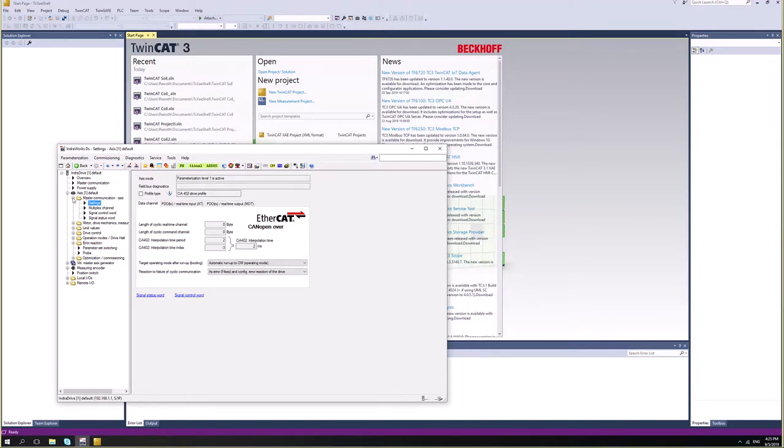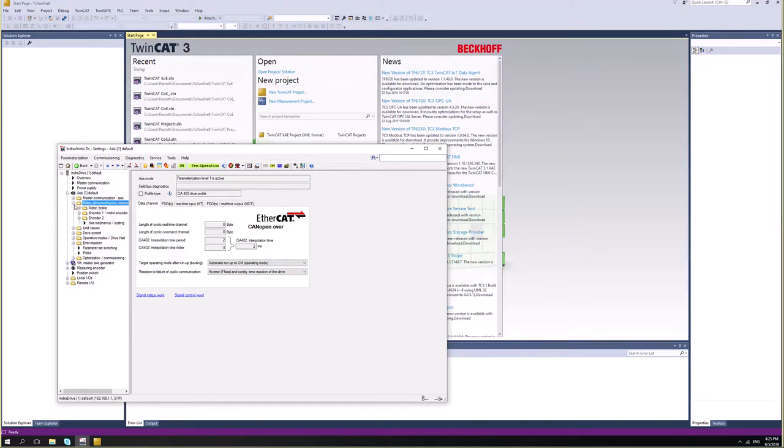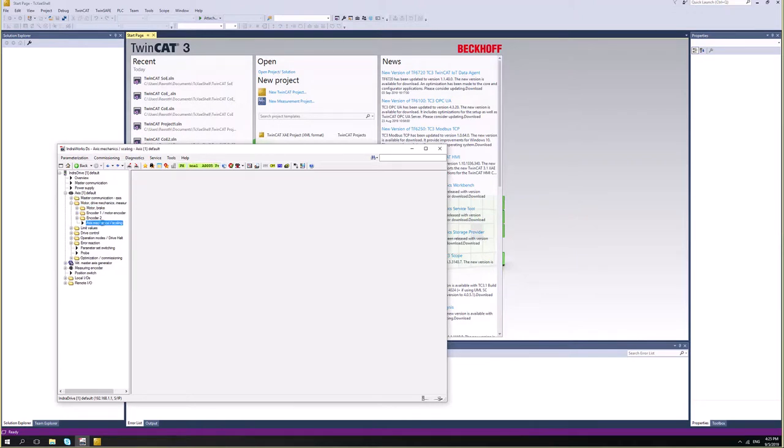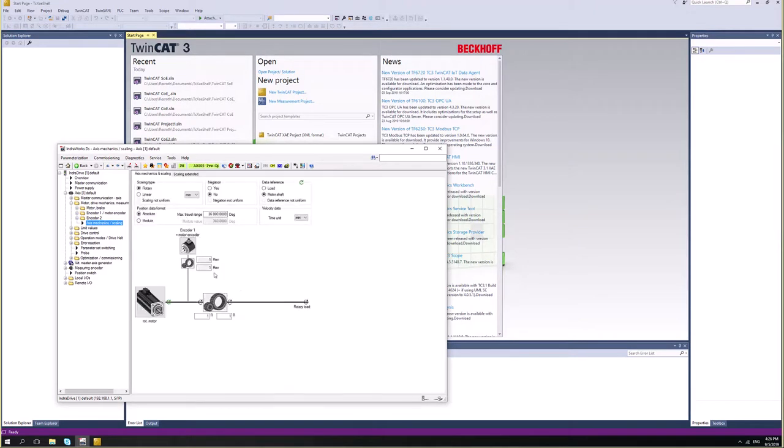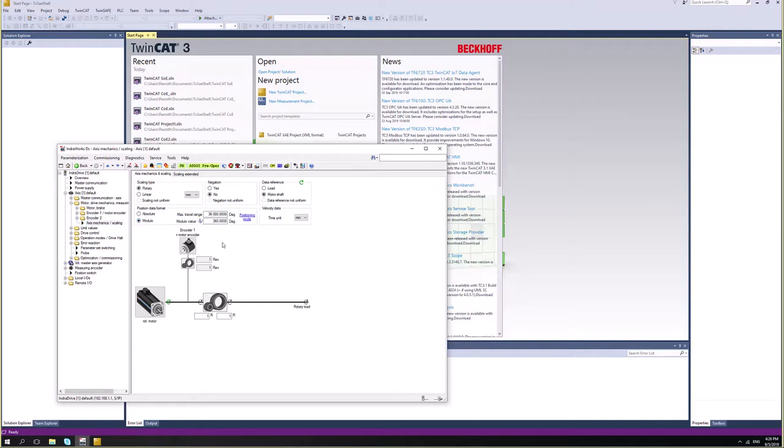Another thing that might be important for us is to check if our scaling, the mechanical, is properly configured according to our machine configuration. In my case it is configured as rotary and absolute. Let's say that I want to run modulo. So I'll just check modulo here. And I have like a rollover of 360 degrees. So it's good for me.